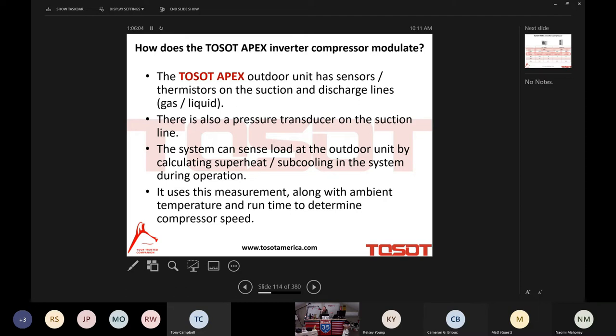Okay, so this is how the Apex controls the modulation of the compressor. The Apex outdoor unit has sensors, thermistors. I've showed you them, right? On the suction and the discharge line, your gas and liquid. There's also a pressure transducer on the suction line. The system can sense the load at the outdoor unit by calculating superheat and subcooling in the system during operation as a result of these sensors, my friends, right? It uses this measurement along with ambient temperature and runtime to determine the compressor speed, to determine the compressor RPM.